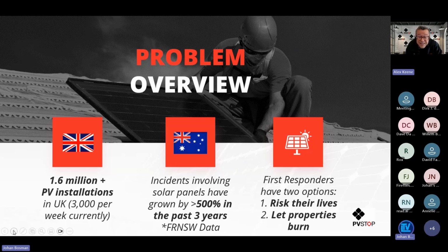They clearly identified there was a live DC current issue with PV panels, and there wasn't an easy way to turn them off. There are methods for partial de-energizing and methods for isolation. Most importantly, from a first responder perspective, you can isolate the AC electricity supply. Solar panels generate DC electricity, which goes to the inverter and converts to AC, so it can be used with standard plug sockets in normal household or business operations. In Australia, they decided it would be a good idea to put a second DC isolation switch at the panel level on the roof, and they saw a 500% increase in incidents involving solar PV systems as a direct result of this regulation.